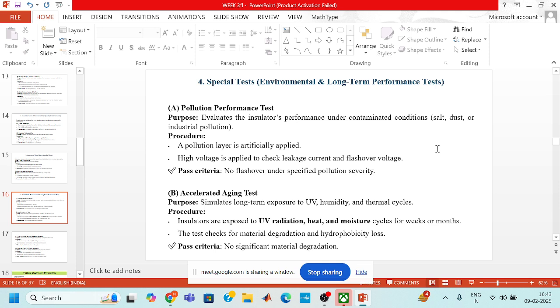So again, if there is no flashover under the specified pollution severity, then it will pass the pollution performance test. Otherwise, we have to perform this test again. Now the B part is the accelerated aging test. It simulates the long-term exposure to ultraviolet (UV) rays, humidity, and thermal cycles. In this test, insulators are exposed to UV radiation, heat, and moisture cycles for weeks or months. Then the test checks for material degradation and hydrophobicity loss. If there is no significant material degradation, then the insulator will pass the accelerated aging test.